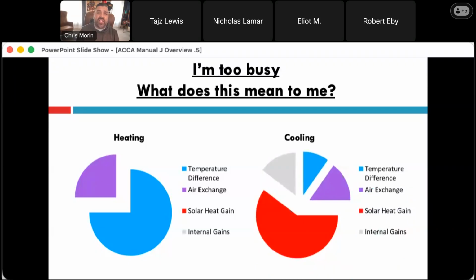When it comes to cooling, you'll notice about 60 to 65% of it is probably solar heat gain, and maybe even more depending on new construction and how much glass is going into those new homes. So air infiltration does actually take into account probably 15, maybe even 20% of your heat gain. Temperature difference, because we typically design to a smaller temperature difference in cooling versus heating, outside to inside, ends up making up a much smaller sliver. But when we talk about cooling gains, we also have to take into account the internal gains. So these are the things that impact the load the most. Don't get me wrong.